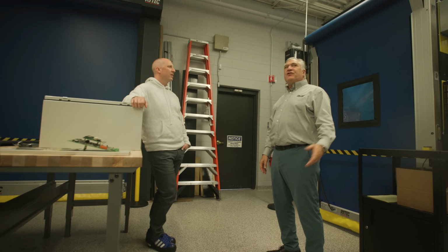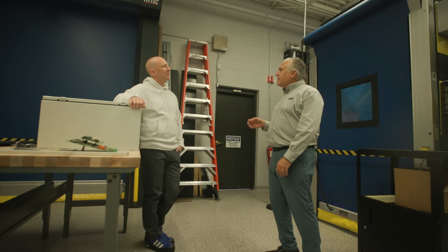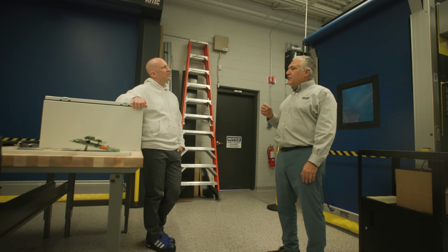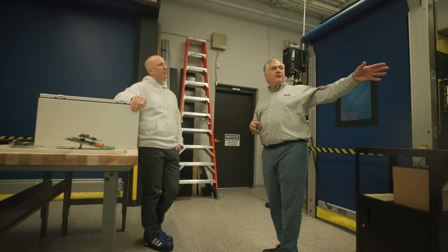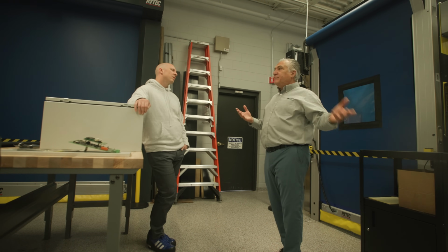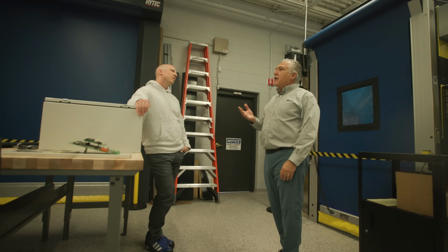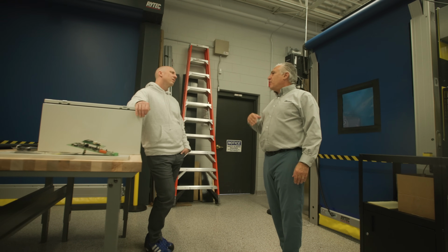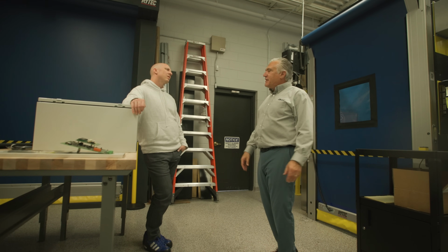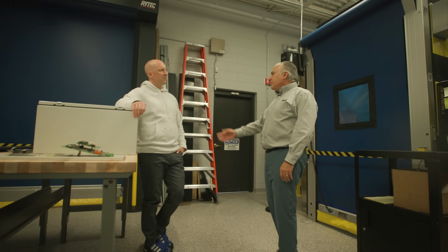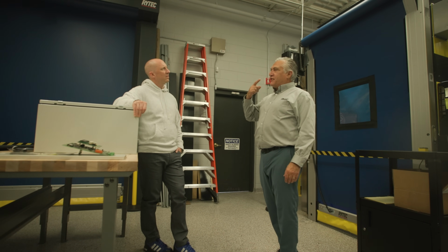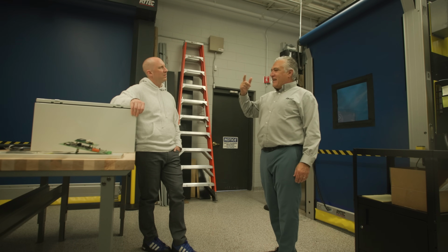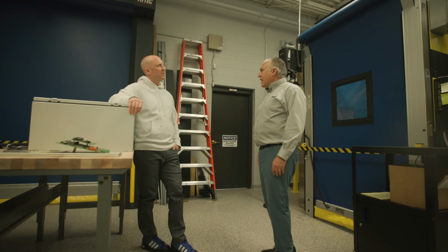Generally, with these doors, the thing that's always overlooked isn't so much how much current they draw, it's how much inrush. A spiral door like that will run on 230 volt at right around 7.5 to 8.5 amps. You're like, well, a 20 amp circuit, no problem, right? Every time it starts, it could draw as much as 18 amps.